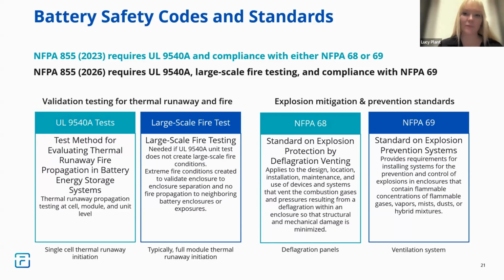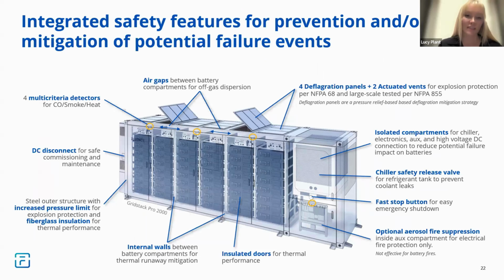If we go to the next slide. This just gives you an indication from our GridStack Pro system of some of those safety measures that we've integrated. So you can see at the top of the system, the things that look like sunroofs. They are our passive deflagration panels. They're going to open up, like a sunroof. So the first time that any gas is detected, those are going to open up and give a way for that gas to be released in a controlled way. More like a kind of chimney, if you like, on the top of the battery system itself. Next to that are the active deflagration panels. As the pressure starts to build up within this container, those will blast off. So again, that's popping like a balloon, not exploding like a grenade.